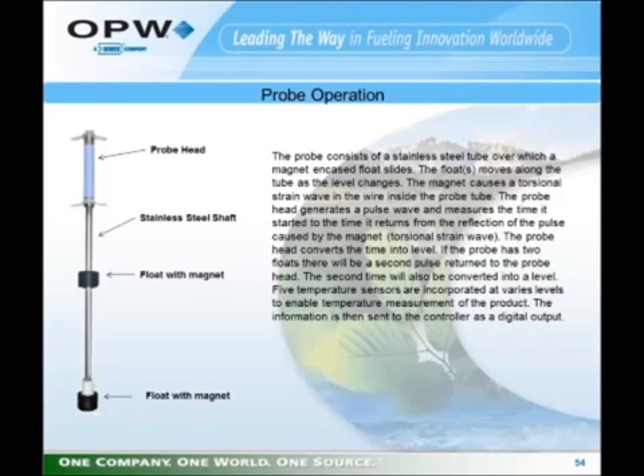So basically you see a return pulse for the product magnet and a return pulse for the water magnet. The system times the difference from when the pulse left the head until the reflected pulses came back, and using those measurements it is able to compute heights in the tank for both the magnet for the water float and the magnet for the product float.